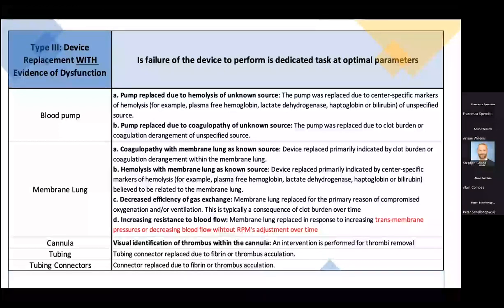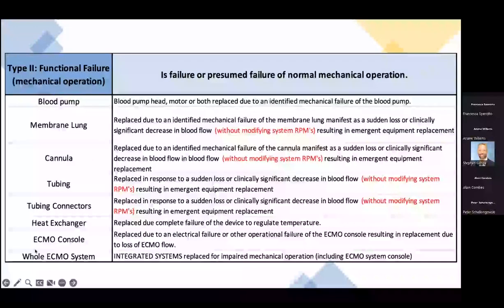C is a decreased efficiency of gas exchange. So the membrane lung is replaced for the primary reason of compromised oxygenation and or ventilation, and this is typically a more common consequence of clot burden over time. And D is increasing resistance to blood flow, as the membrane lung is replaced in response to increased transmembrane pressure or decreasing blood flow without RPM adjustment over time. For the cannula, sorry.